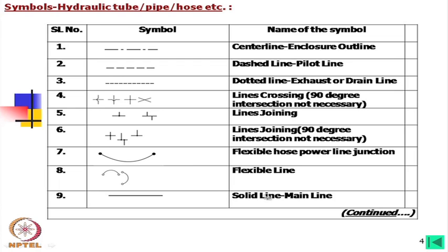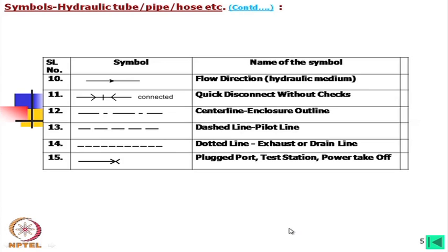The solid line usually means the main line. If an arrow is given, this indicates the direction of flow, usually of hydraulic medium — if the triangle is filled, it is hydraulic; if not filled, it is air or gas. This is a quick connector or disconnector symbol.